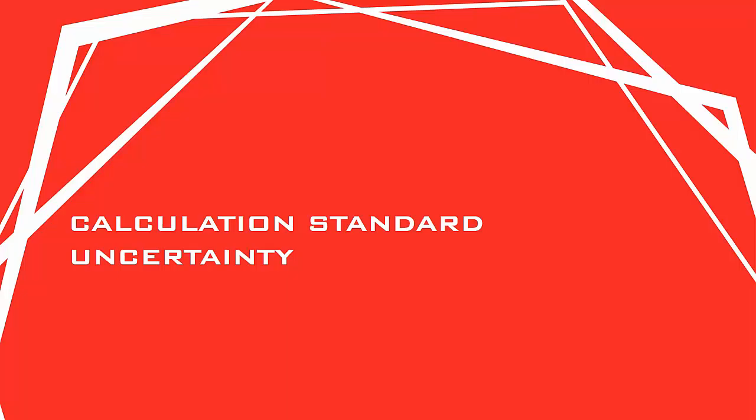The next thing that we're going to need to do is how do we convert these individual uncertainty values from each component into a calculation standard uncertainty, such as CV uncertainty or line density uncertainty. It's all dependent on the calculation standard that we have. I'm going to talk mainly about the ISO 6976 calculation on the CV, but the exact same principle can be applied to any other calculation that has gas composition as its input.